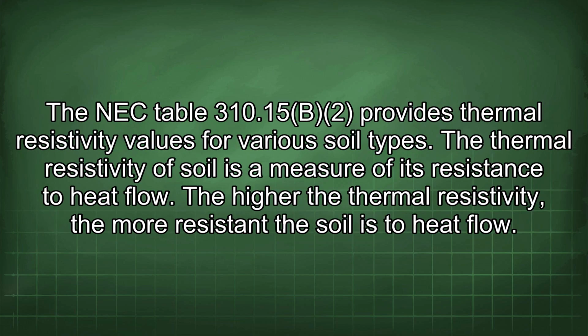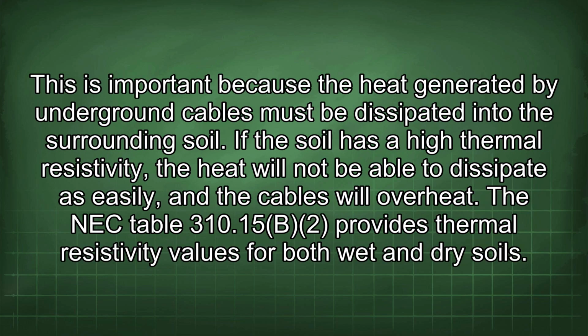The NEC Table 310.15(B)(2) provides thermal resistivity values for various soil types. The thermal resistivity of soil is a measure of its resistance to heat flow. The higher the thermal resistivity, the more resistant the soil is to heat flow. This is important because the heat generated by underground cables must be dissipated into the surrounding soil.